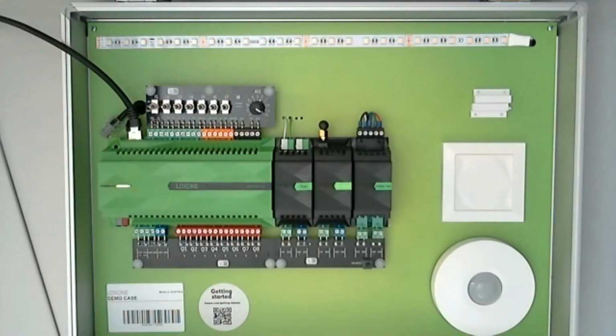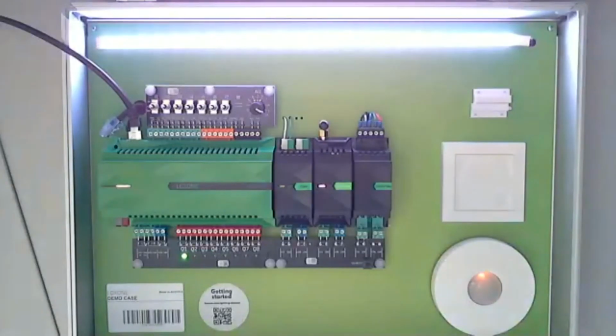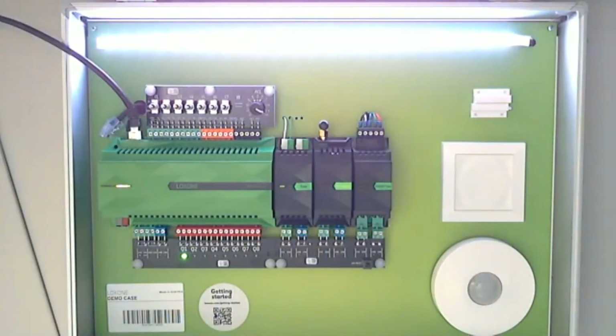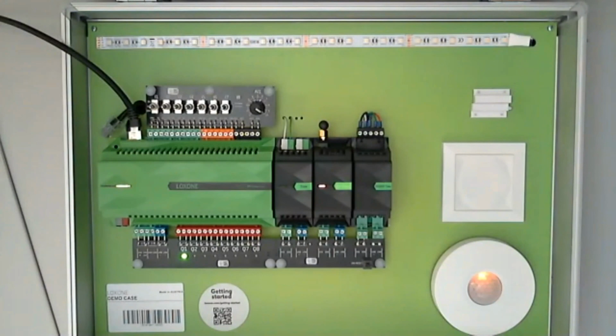And what I've just thought is actually waiting for all of that to happen again, 30 seconds each time, is probably a little bit too long. So I'm going to shorten that reaction time to 5 seconds per person, and then make it 20 seconds maximum on the main alarm, and then save that in, just so that I don't have to make you sit around and wait here for 3 minutes just to watch some lights flash. And there we go. Now that I've shortened that delay, you can see that the lights are going off.